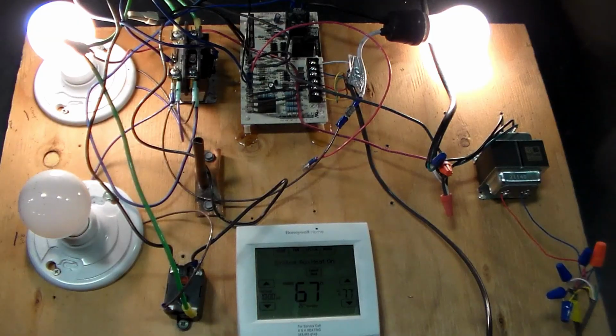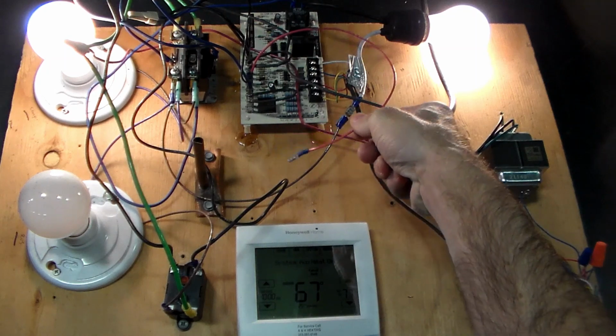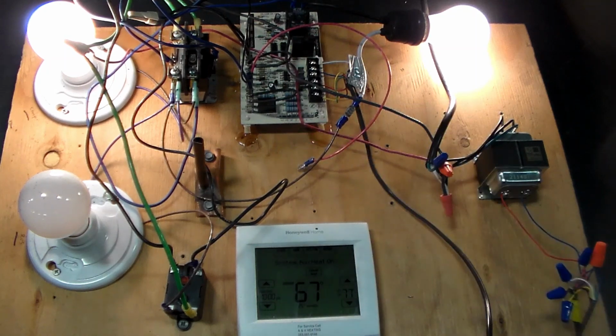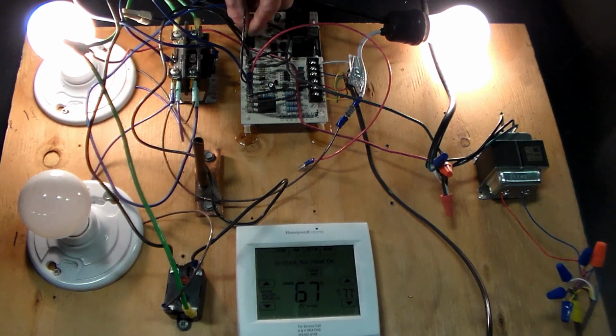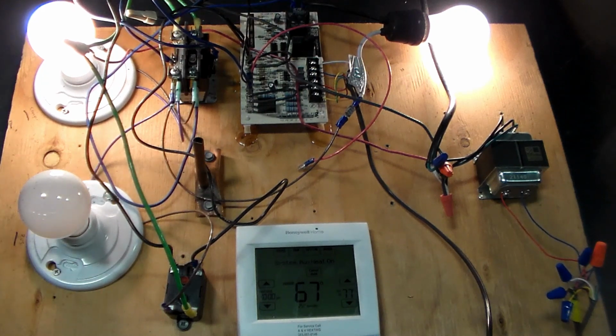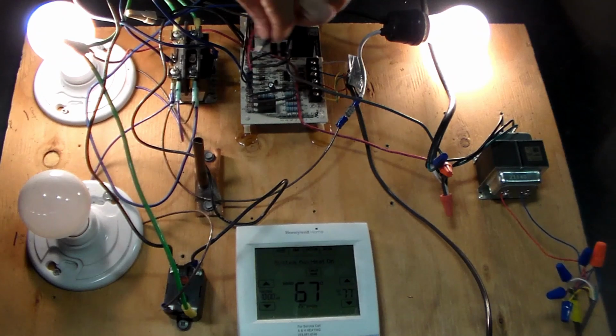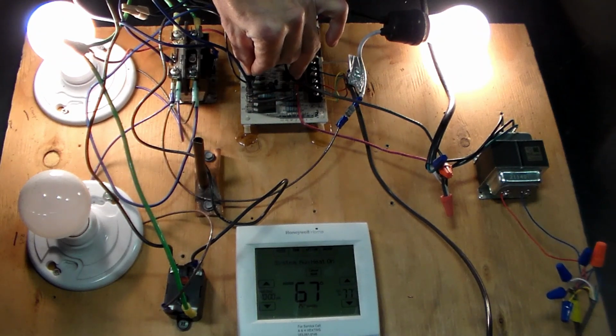Now just to show you, I have disconnected the jumper on the defrost sensor, and look what happens when I jump it into defrost test mode now. Nothing. Because you remember, you have to jump out that defrost sensor first to trick it into thinking it needs the defrost.